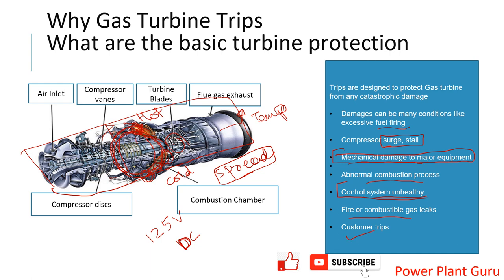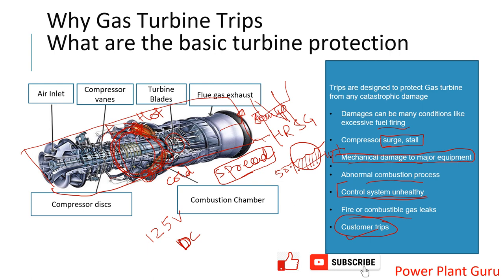The last one is the customer trip, where many people get confused. For example, if you are connected to an HRSG that has a steam drum where you need to maintain a 50% water level, and due to some reason the water level drops down to the HRSG trip level — say 10% — and you are not able to cut off the GT damper position to the HRSG, it will send a stop signal to the GT to protect the HRSG equipment from further high-temperature water starvation damage. That is one example of a customer trip.